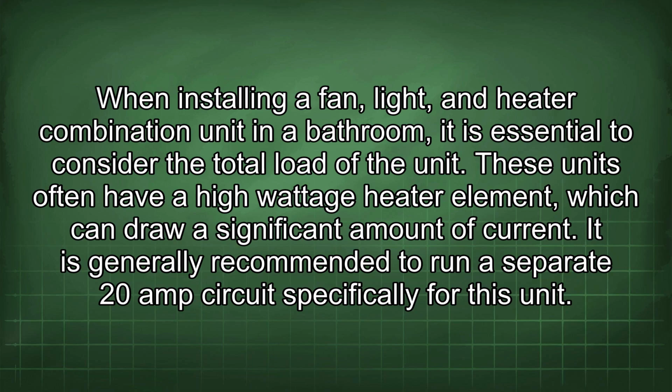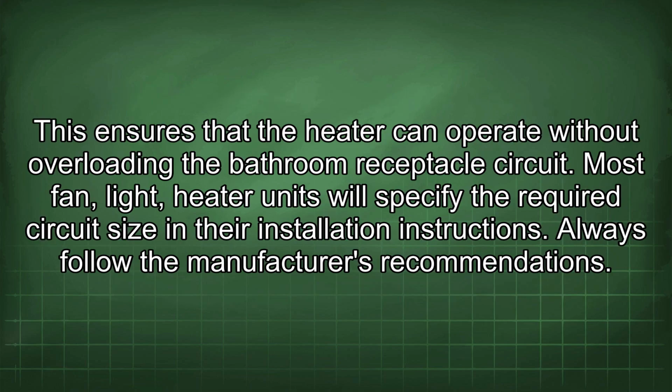When installing a fan, light, and heater combination unit in a bathroom, it is essential to consider the total load of the unit. These units often have a high wattage heater element, which can draw a significant amount of current. It is generally recommended to run a separate 20-amp circuit specifically for this unit. This ensures that the heater can operate without overloading the bathroom receptacle circuit.